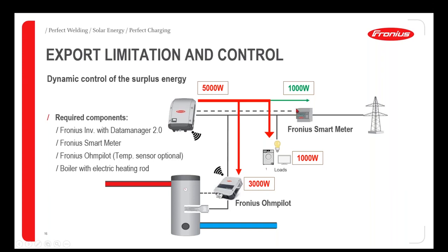In order to provide export limitation, to stop energy going back to the grid, the smart meter values are simply used to throttle back the inverter output. So what we see is a reduction in the output of the inverter. Obviously, the bigger the battery or the bigger the loads on site, the less you have to throttle back the inverter. So adding all these extra devices, the smart loads, the Ohmpilot, means that your inverter can work at full power rather than having to throttle back under export limit conditions.